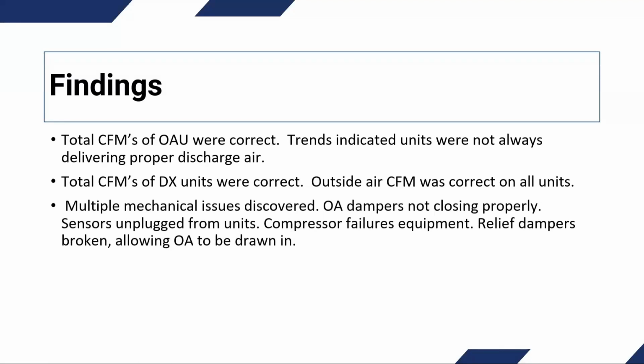But we did discover multiple mechanical issues. We found some dampers that were not closing properly. We found a myriad of sensors that were unplugged on units, whether it be sensors or modules. We had a lot of compressor failures on equipment, relief dampers that were broken, thus allowing outside air to be drawn in through the relief. So we did find a lot of mechanical issues. It was determined that some of these mechanical issues were failures, and it was also determined that some of these mechanical issues were because the owner just decided, well, let's just disconnect this stuff and see if we can solve the problem ourselves.